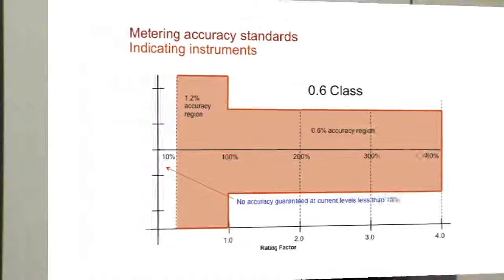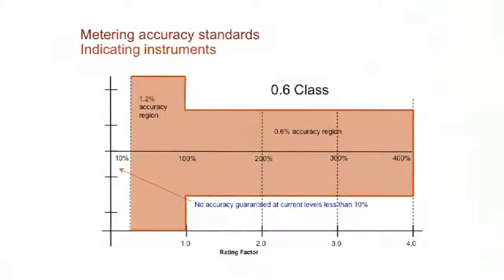What that 1.2 and 0.6 means is that any current transformer in that class has to record current accurately between 1.2% below or 1.2% above what we call nominal current. So if you have a current transformer that's rated a 200:5 ratio, that would have to fall within, in this case at the bottom, 1.2% below or 1.2% above 200 amps.